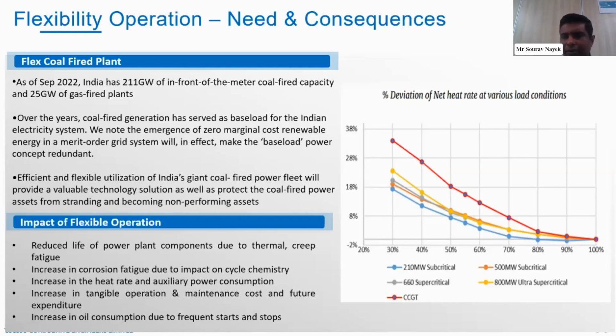If we see the diagram, we have captured, for different ratings of the unit, 210 megawatt, 500 megawatt, 660 megawatt, 800 megawatt, and even at the CCGT level, combined cycle power plant, how the minimum load and the loading condition increase the heat rate. The variation is almost 20 to 25% increase in the coal power plant, and this will go further in the combined cycle power plant.